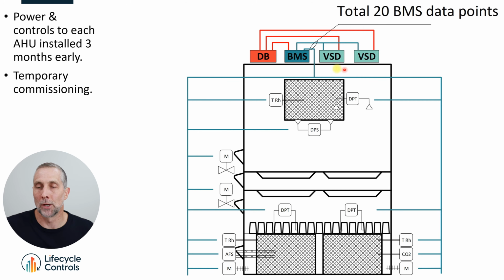You could set the addressing and get them online to the BMS controller and your temporary network controller, get that all commissioned. You could do the high-level interface, map all the points back. You could even probably input off the motor nameplates, the voltage, current, the frequency, the RPM, and maybe, I'm just making this up, but just turn the VSD on, just like 2 or 3% and just do a rotation check. Is the fan turned the right way, then turn the power off again.